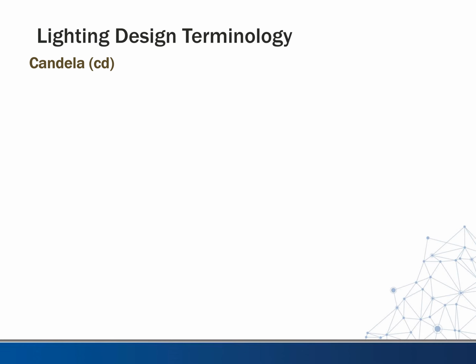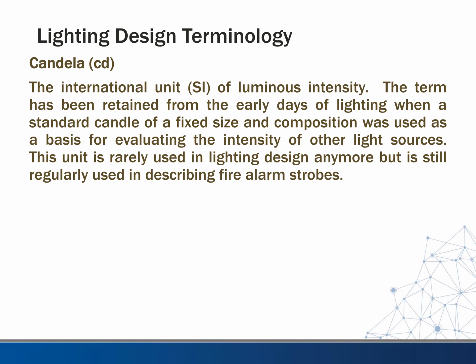Another term is candela. This international unit of luminous intensity is a term that has been retained from early days of lighting, when a standard candle of a fixed size and composition was used as a basis for evaluating the intensity of other light sources. The unit's rarely used in lighting design anymore. However, it is still regularly used in describing fire alarm strobes. So when we get into fire alarm design, you'll see this term pop back up for candela rating.